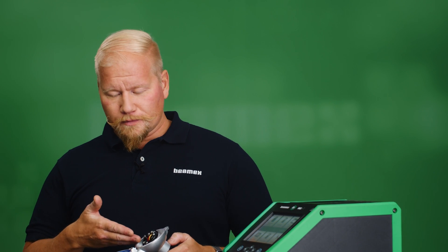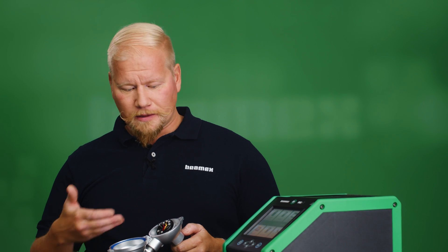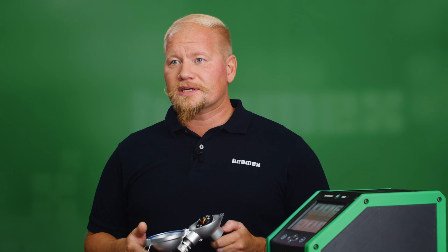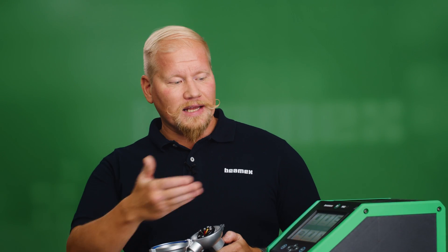To calibrate this package you first need to create the instrument and give it parameters such as ID, calibration range, set points, and error limits. You can do it directly on the MC6T or you can do it in the Beamex calibration software CMX or LOGiCAL, and then send it to the calibrator.